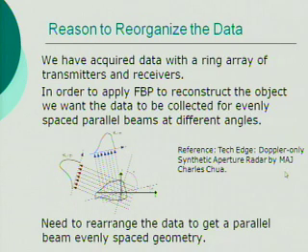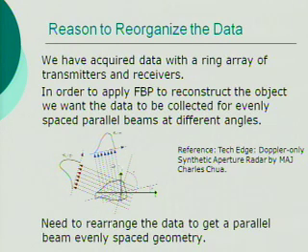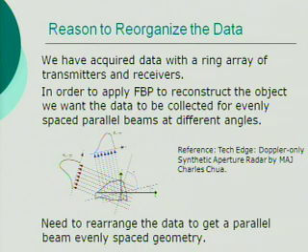But this is not what we want, so we need to do interpolation and manipulation. We acquired data with a ring array of transmitters and receivers, but in order to apply filtered back projection to reconstruct the object, we want the data to be collected for evenly spaced parallel beams at different angles. So we collect data for different parallel paths, then rotate to a different angle and collect again. We need to rearrange the data to get a parallel beam evenly spaced geometry.